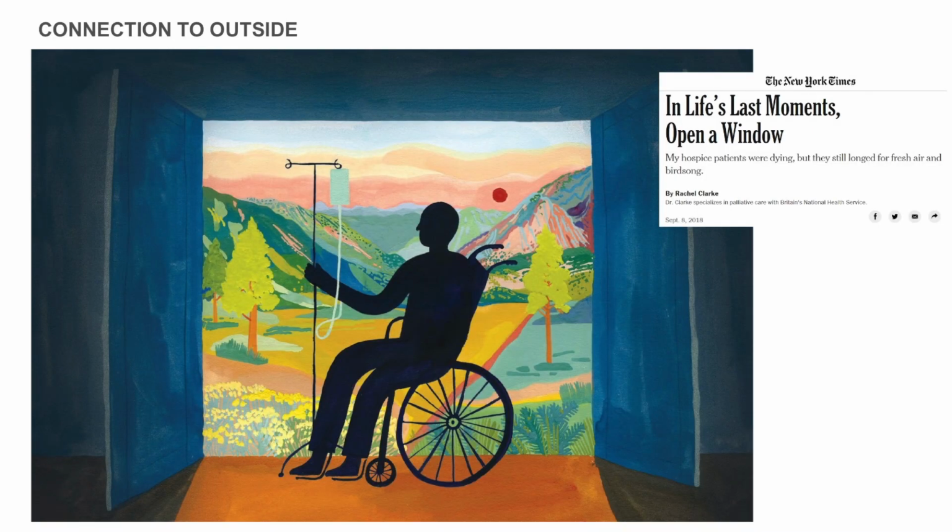And so from that connection to the exterior, one of the things we've also become interested in is getting natural ventilation in patient rooms. It's something that obviously is not very common, and actually for a while wasn't even allowed under the FGI guidelines, but recently has been allowed. And so what we've been trying to do is to understand, what are the barriers to getting this into a project so that we can understand them better, and how would that actually impact design? How would we design a space to meet these requirements, still maintain the air change rates that are required, but also allow patients to have that connection?